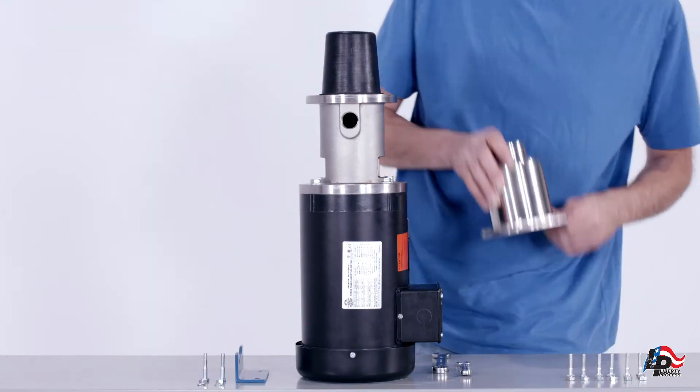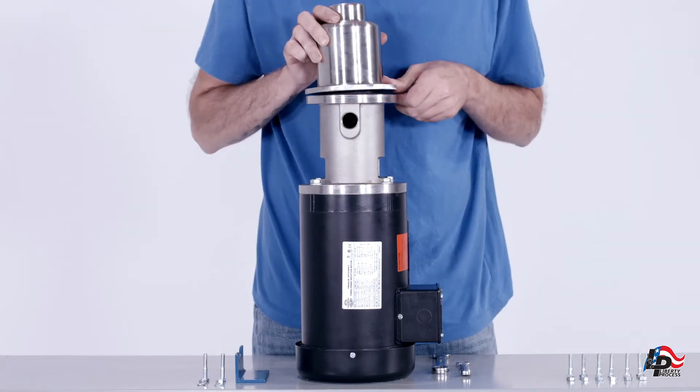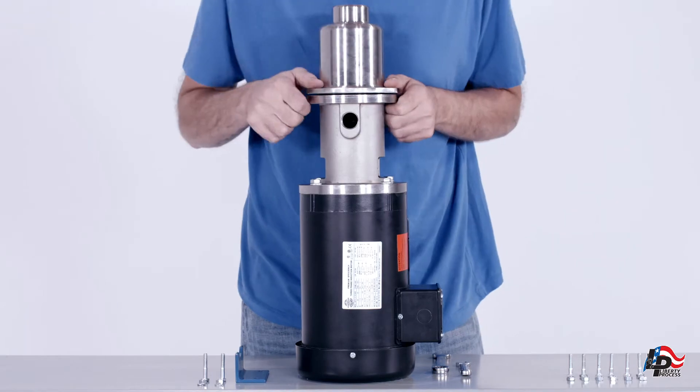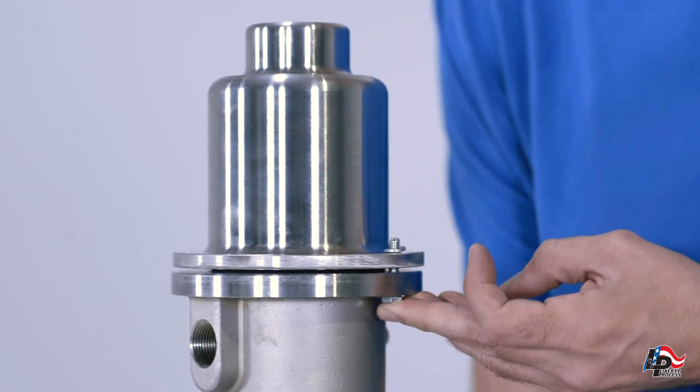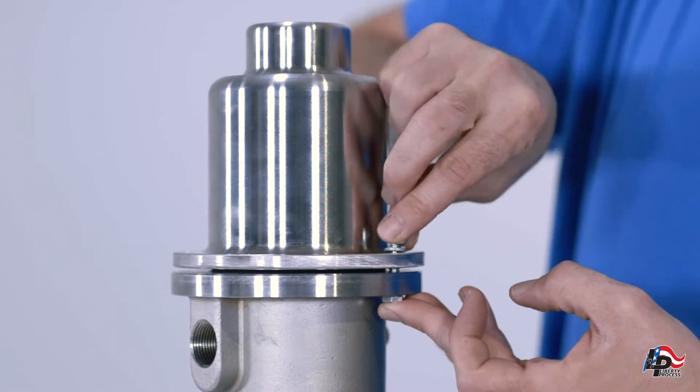Install the suction casing onto the pump assembly. Bolt the suction casing down using the seven sixteenth inch bolts, saving the two largest bolts for the foot assembly.